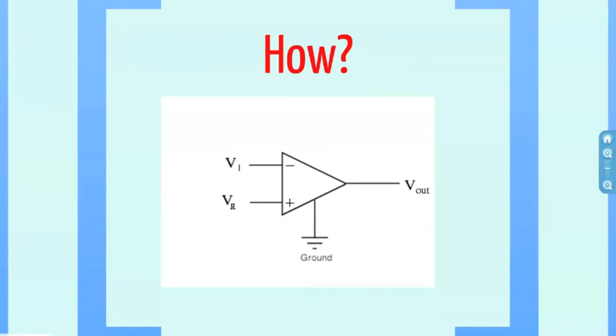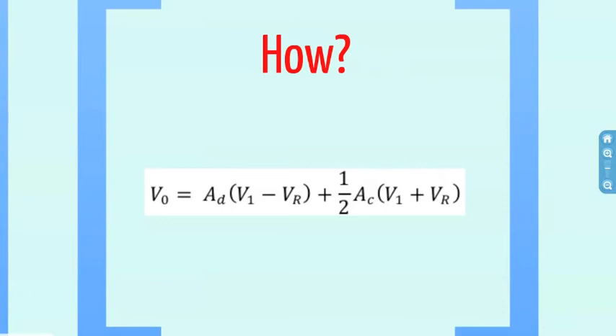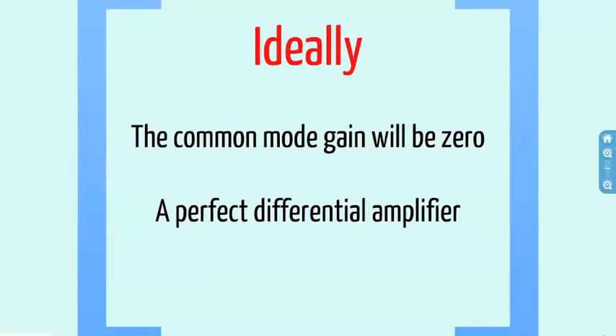This is a simple diagram of a differential amplifier, where V1 is the input electrode, Vr is the reference electrode, ground is the ground electrode, and Vout is the output of the differential amplifier. This is the differential amplifier equation, where V0, V1, and Vr are as just described. Ad is the differential gain and Ac is the common mode gain. Ideally, Ac — the common mode gain — will be zero, meaning almost no noise is present in the output V0. This would be a perfect differential amplifier. However, this is very rarely the case.